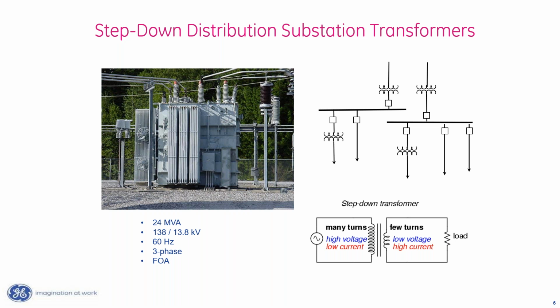It does two things for us as well. It transforms that voltage so that we don't have to have some sort of a massive transformer outside our home to get down to 120 in our home. But the other thing it does for us is that the distribution system is subject to a lot more ground faults than the transmission system because the insulators are smaller. Their insulators are for 12 kV versus 230 kV. So a heron has the wingspan to span across an insulator at 230 kV, but a squirrel can span across a 12.47 kV insulator. So squirrels can cause lots of ground faults.